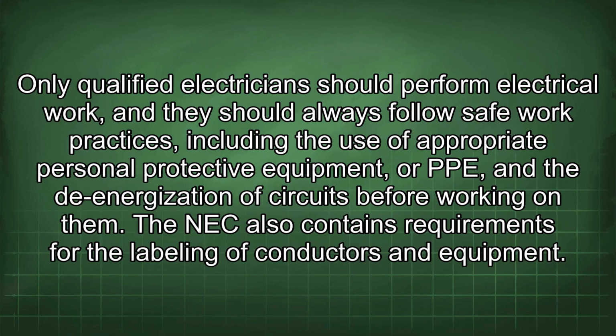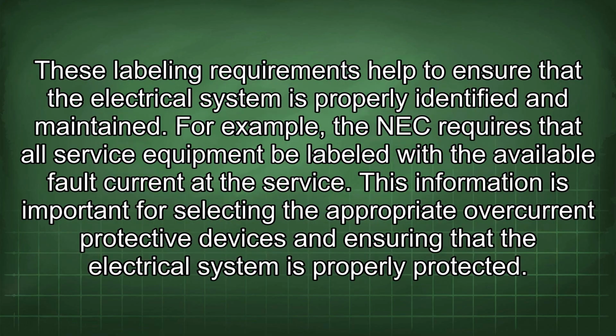The NEC also contains requirements for the labeling of conductors and equipment. These labeling requirements help to ensure that the electrical system is properly identified and maintained. For example, the NEC requires that all service equipment be labeled with the available fault current at the service. This information is important for selecting the appropriate overcurrent protective devices and ensuring that the electrical system is properly protected.